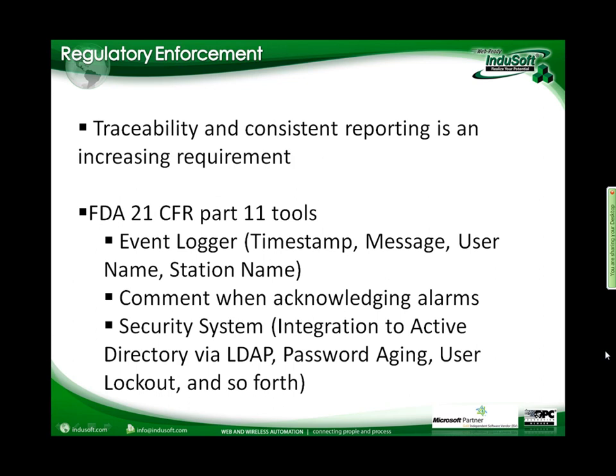We are seeing more regulatory enforcement — traceability and consistent reporting are increasing requirements. Especially in food and drug applications, FDA 21 CFR Part 11 is being more and more enforced. In the Software Studio, we provide all the tools needed to create a fully compliant application: the event logger saves all critical user actions with timestamp, message, user name, and station name. Users also have the option to enter a comment when acknowledging alarms, as required by FDA regulation.